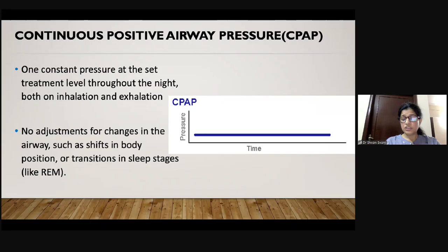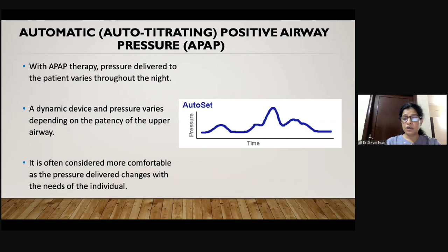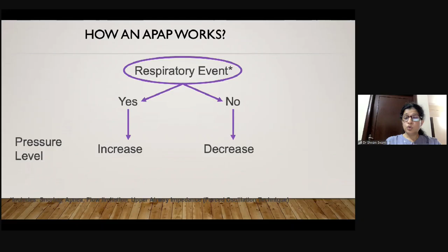However, what this equipment basically does is the algorithm is set in a way that it reads the airflow limitation, and depending upon the patency of the upper airway, it increases or reduces the pressure. It is often considered more comfortable because the pressure delivery is changing dynamically as the patient's airflow obstruction is changing with the individual needs. So of course, when there is a respiratory event, it increases pressure. When there is no event, it gradually starts reducing the pressure, and hence it's considered more comfortable.